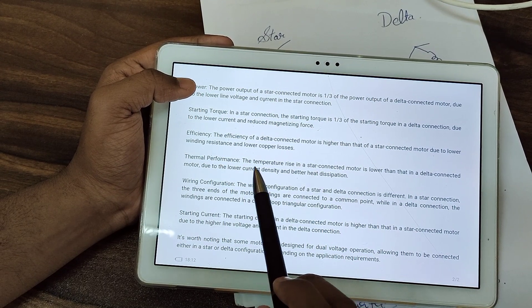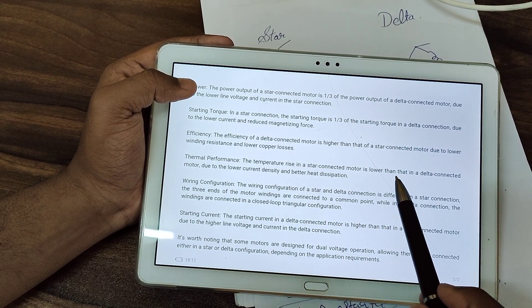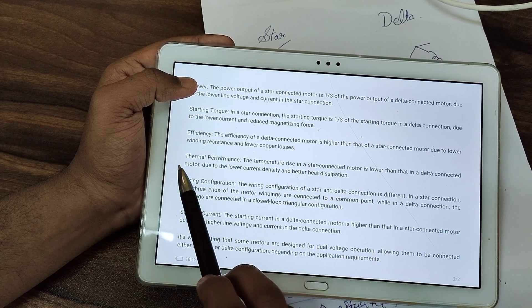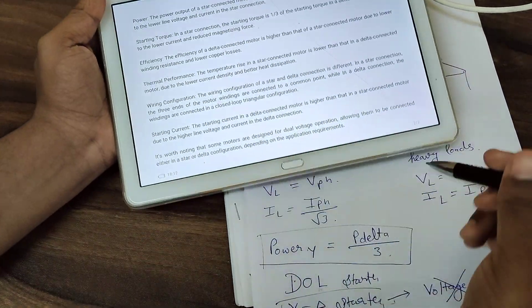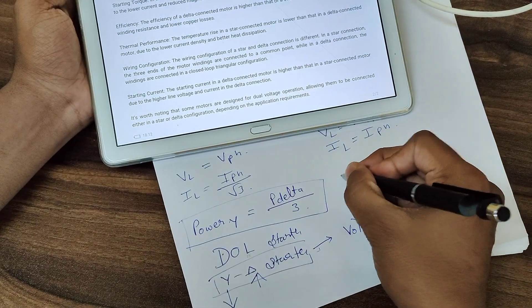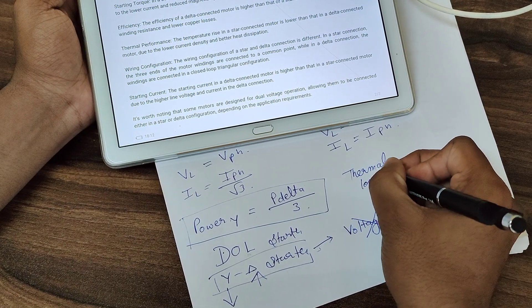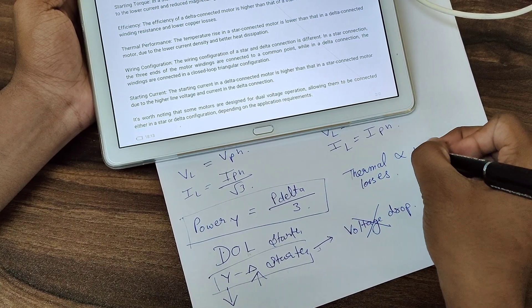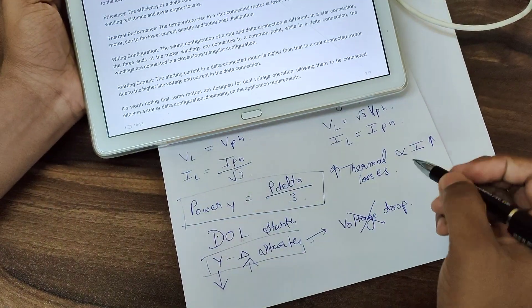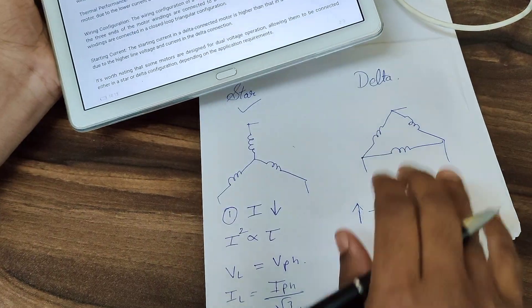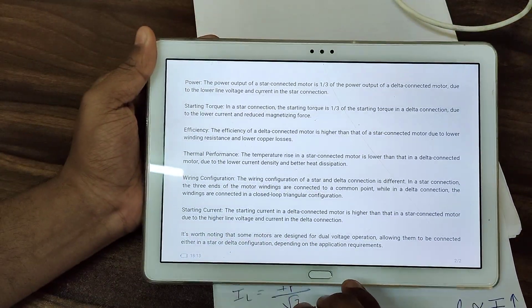Regarding thermal performance: the temperature rise in a star-connected motor is lower than that in a delta-connected motor, due to lower current density. Current is directly proportional to thermal losses. If the current is higher, as in delta, then the thermal losses will also be higher.